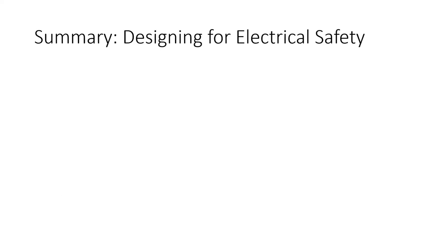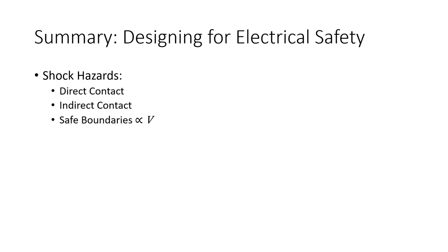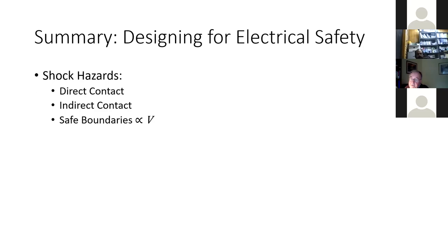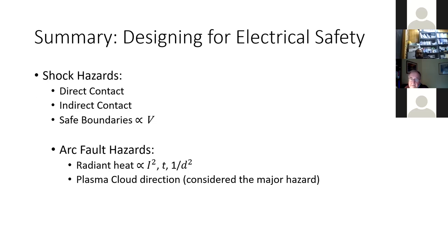So in summary, when we're designing for electrical safety, we need to bear in mind the shock hazards, both by direct contact and indirect contact. And remember that the safe shock boundaries are determined by the voltage. And we also need to bear in mind arc fault hazards, where radiant heat is proportional to the energy divided by the square of distance. The plasma cloud, the direction in which the plasma cloud is likely to move, is considered the major hazard.